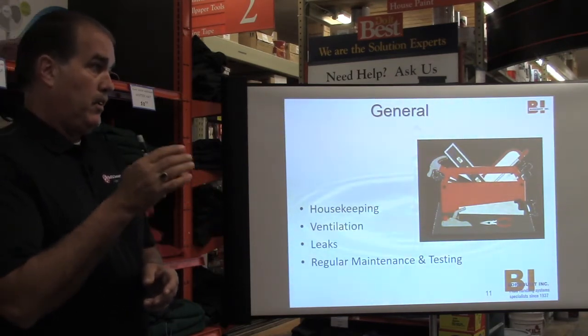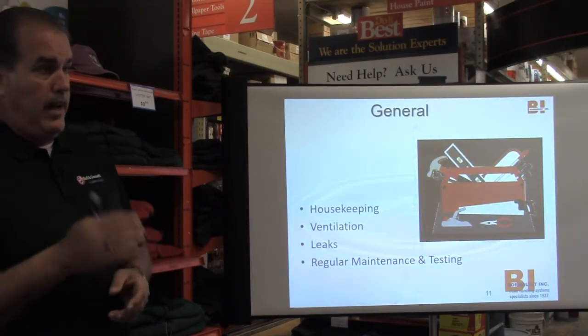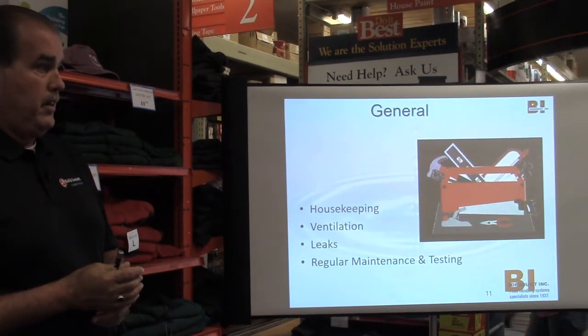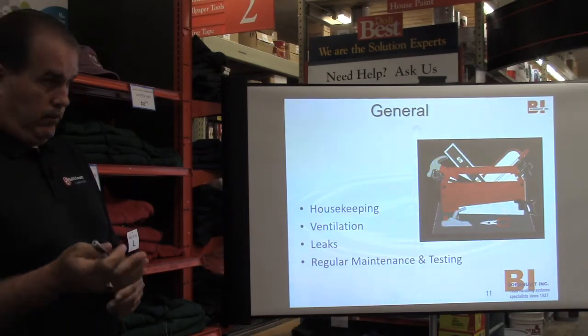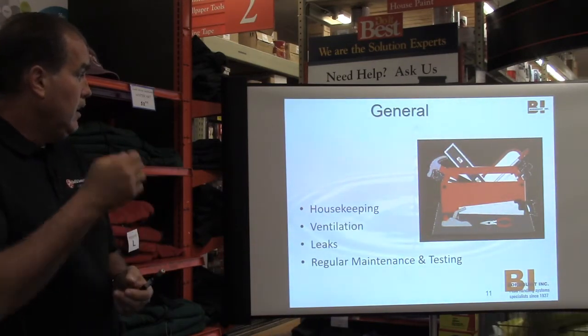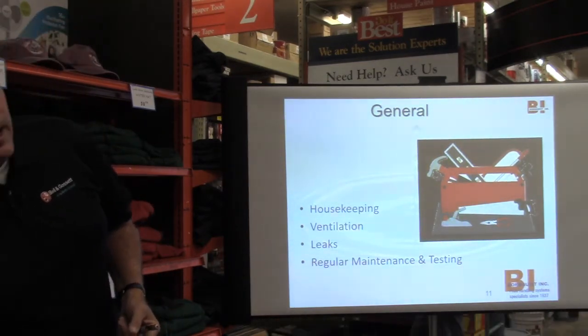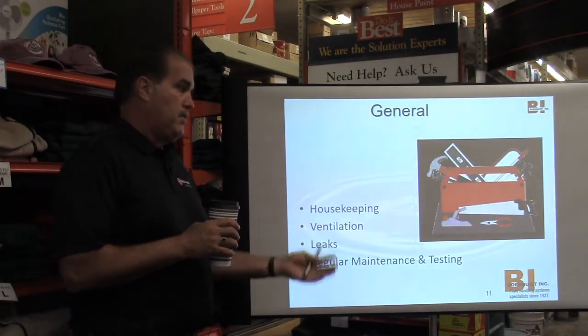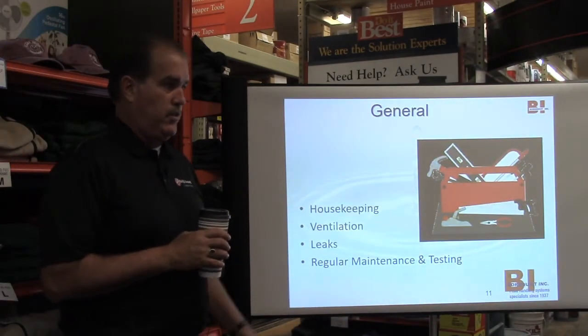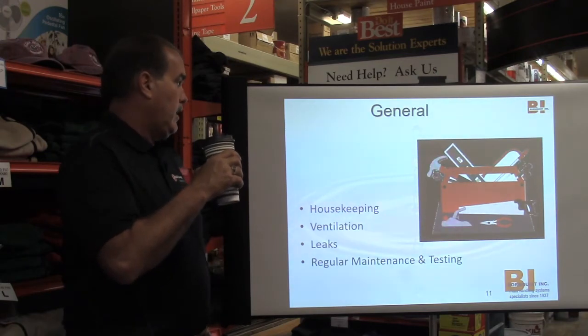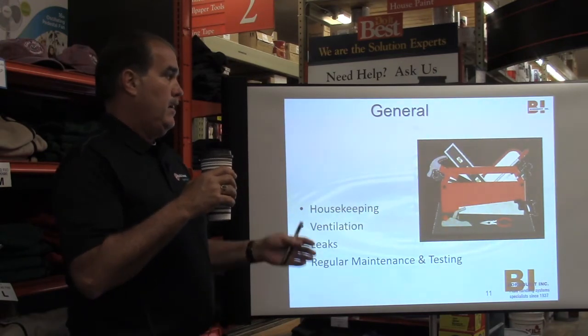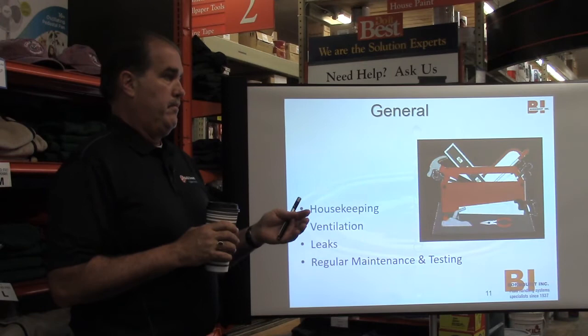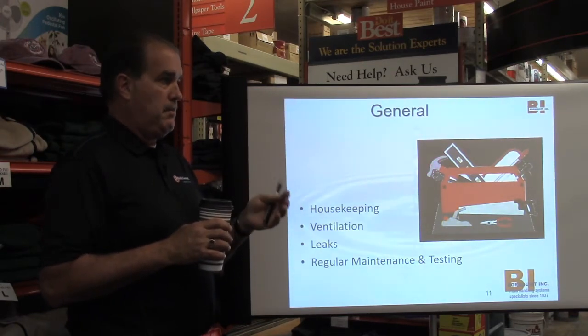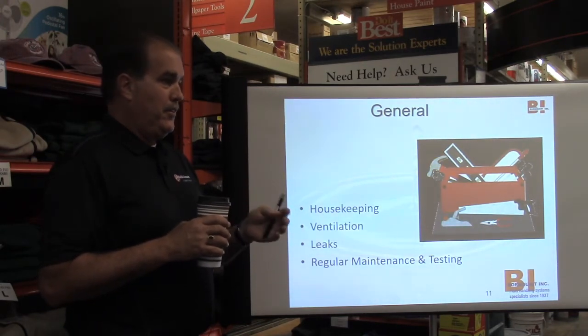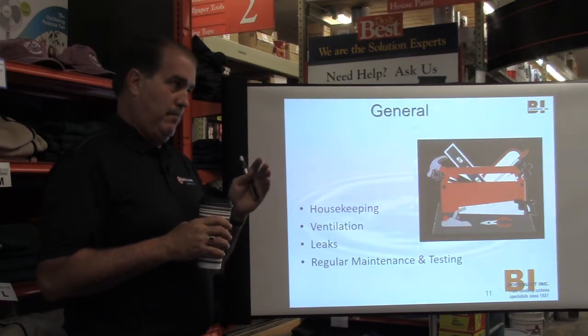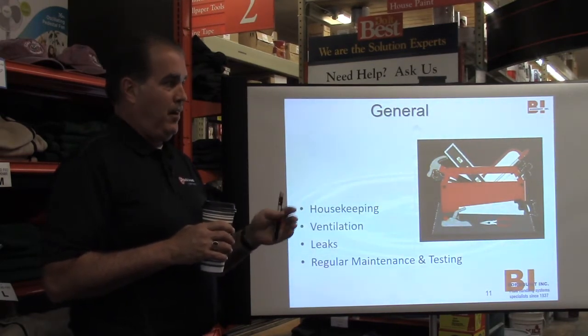On a steam system, your water feeder is going to turn on periodically. That is normal, very normal operation, so you should expect fresh water to come in. And that's where we get into a little bit of water treatment. I'm not going to go into different types of water treatment or different manufacturers that are out there. All I can tell you is this: if you have a system that's been functioning fine for many, many, many years, introducing water treatment may actually hurt you rather than help you.